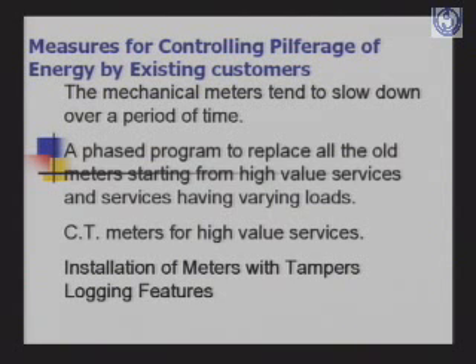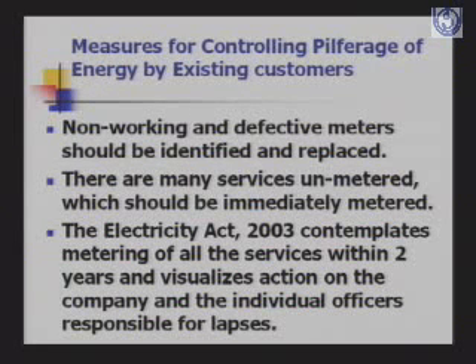Then what are the measures that we can take for controlling pilferage of energy by existing consumers? They are consumers, but they tend to tamper the meter. So the mechanical meters tend to slow down over a period of time. We should have electronic meters for the consumers. We should have CT meters for high value services and install meters with tamper logging features. The electronic meters should be such that they have tamper logging features. Non-working and defective meters should be identified and replaced. Unmetered supply should be metered immediately.